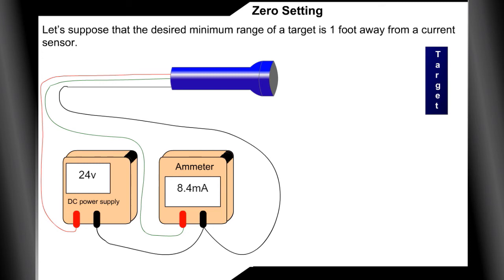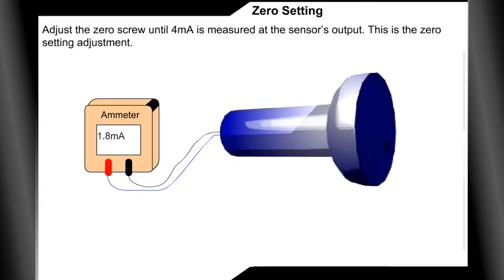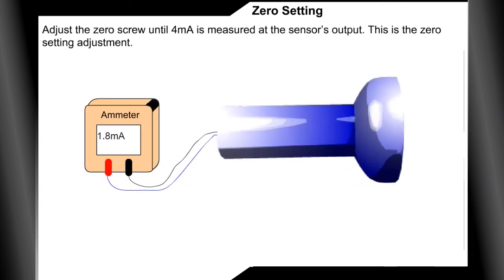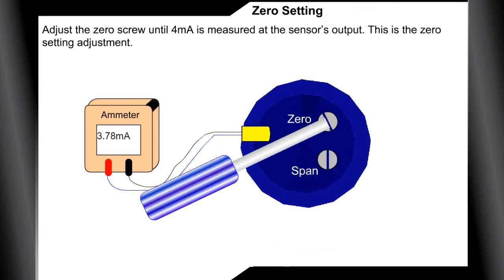Let's suppose that the desired minimum range of a target is 1 foot away from a current sensor. Adjust the zero screw until 4 milliamps is measured at the sensor's output. This is the zero setting adjustment.